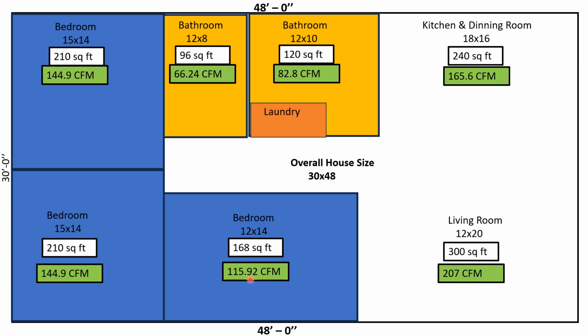And then what I would do is add all these numbers up, and that's how much I would set my capacity for. Now, that probably just threw a bunch of people for a loop when I said add those numbers up and set my capacity at that. You're thinking, what are you talking about? Well, that's why we're doing this podcast, because so many installers would probably stop right there. And I've seen installers that would say, well, this room looks like a 7-inch.